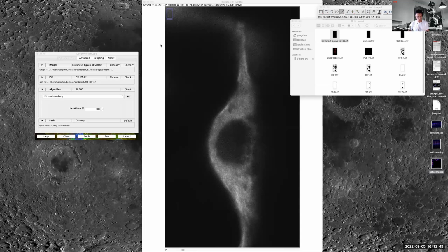This could be because, for example, the front lens of the objective was knocked out of alignment, or there's dirt or some other misalignment in the optical path. In this situation, a simulated PSF wouldn't account for these aberrations, and your deconvolution might be inaccurate. So if you're serious about deconvolution, I believe you should always obtain the experimental PSF wherever possible. But nevertheless, you can simulate a PSF if you wish. To do that, you could go to the PSF Generator plugin in Fiji.